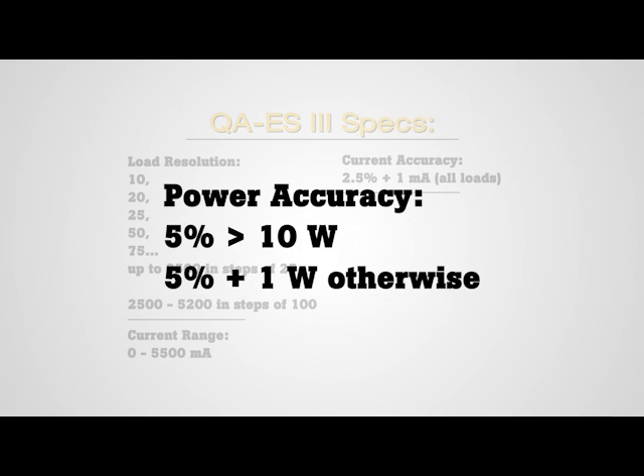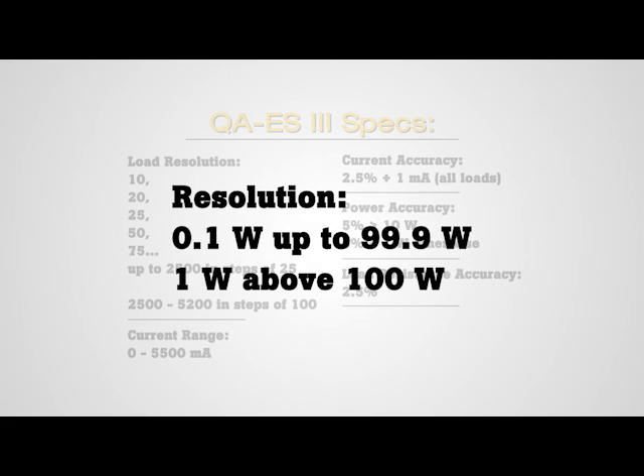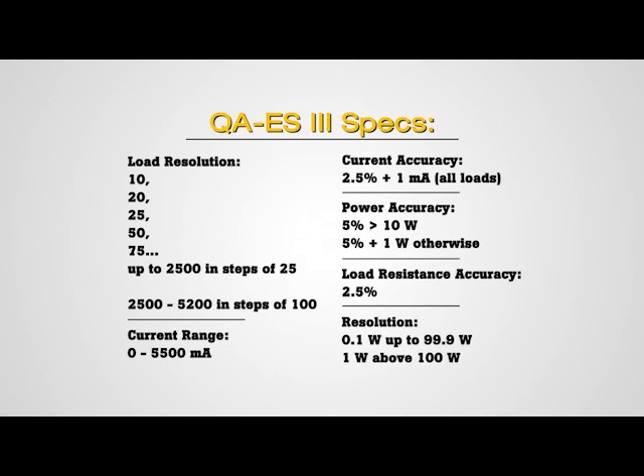It's exceptionally accurate with generator output power accuracy of 5% greater than 10 watts, and 5% plus 1 watt otherwise. In addition, it provides a load resistance accuracy of 2.5%. The QA-ES III is also highly precise with a tenth of a watt resolution up to 99.9 watts, and 1 watt above 100 watts for power measurement.